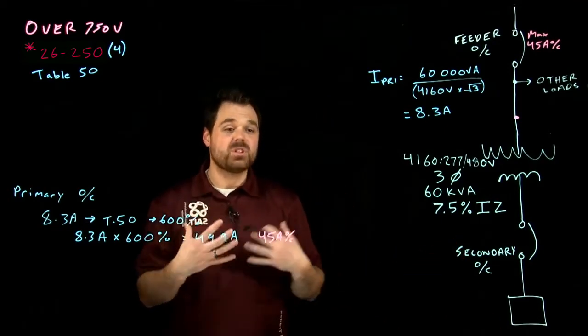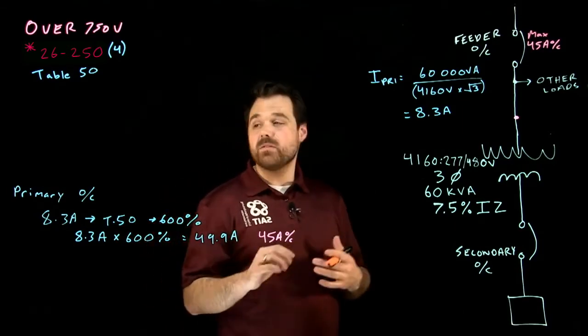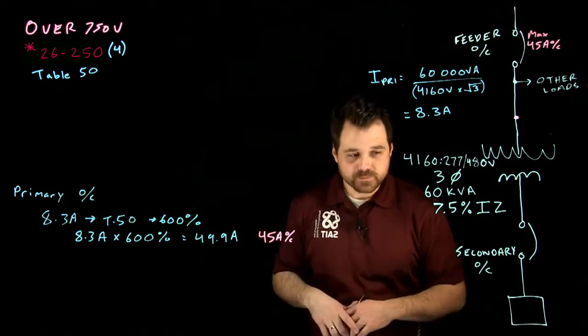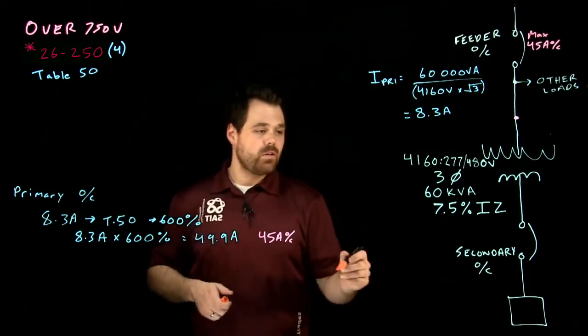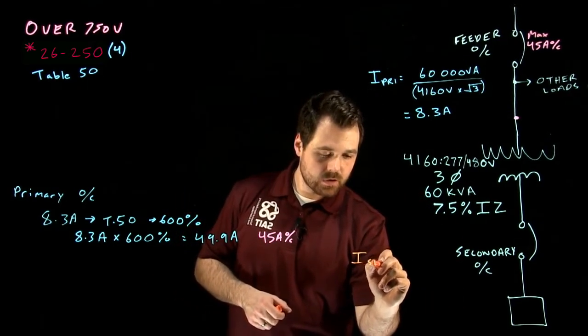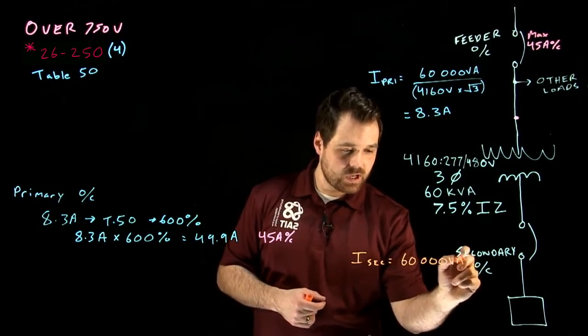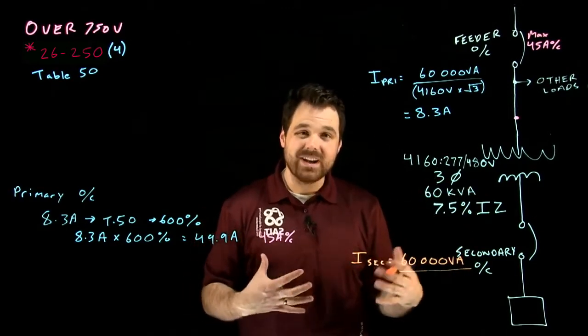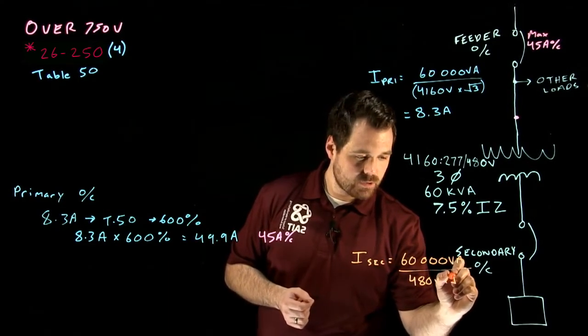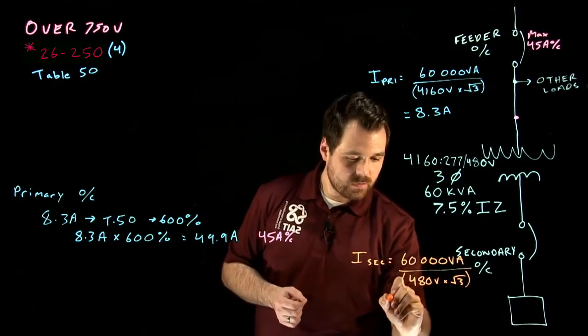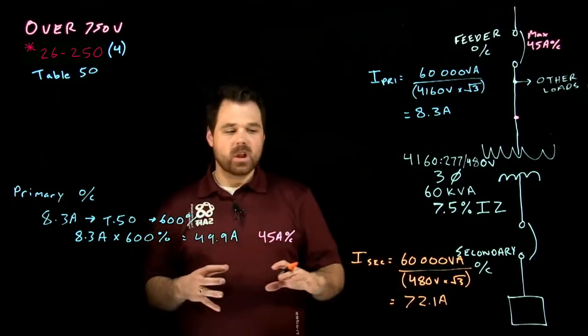Where it gets a little more interesting is talking about the secondary. With the secondary, we're still in subrule 4. It tells us the same thing. It's going to be based off of table 50, 26-250, subrule 4. What we want to do is we need to know our secondary current. I secondary is going to be the same thing. 60,000 VA divided by our 480 or our line voltage, times root 3, which gives us a secondary current of 72.1 amps.